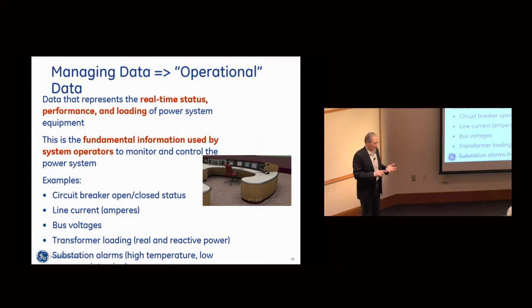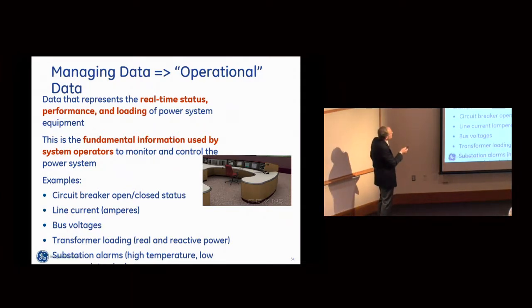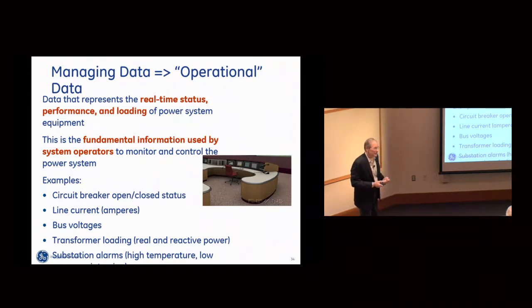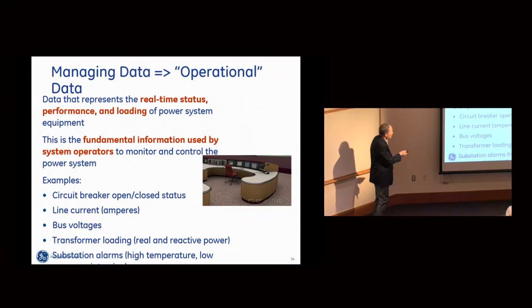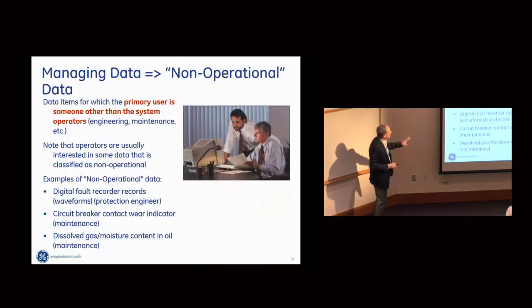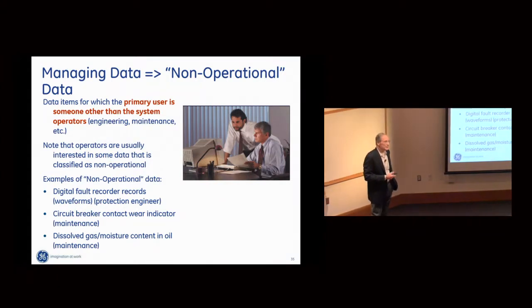It's the stuff the power quality group or asset management group, the planning engineers, could use. Operational data is what operators need in the control center — real-time status, performance, loading — a time series of points at the scan rate of the SCADA master: circuit breaker status, line current, bus voltages. Non-op data's primary user is someone other than the system operator — digital fault recorder records, circuit breaker contact wear, dissolved gas in oil. The sexiness of these devices, the differentiator across vendors, is right here — it's not the operational data, it's this stuff.